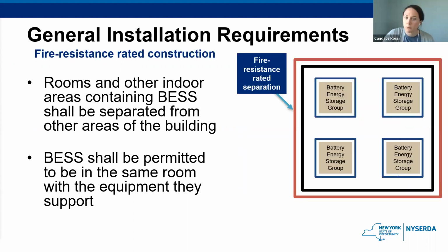Here we have that rooms and other indoor areas containing energy storage systems should be separated from other areas of buildings and shall have a 2-hour minimum fire rating for all installations. The fire protection should also include the ceiling of the room that they're in, but this is not required for walk-in containers. Also, for indoor areas, energy storage systems shall be permitted to be in the same room as the equipment they support. I think this requirement might be pretty obvious why, but you definitely want to ensure that if there is an incident concerning fire, that there is enough time via the fire rating for the building to be evacuated to protect human health in general.